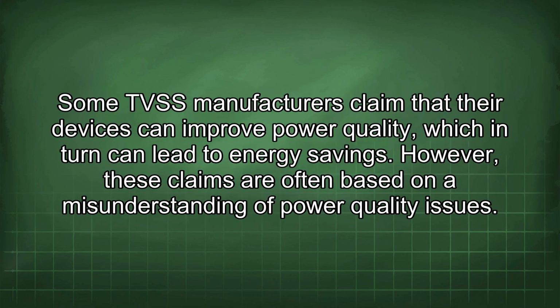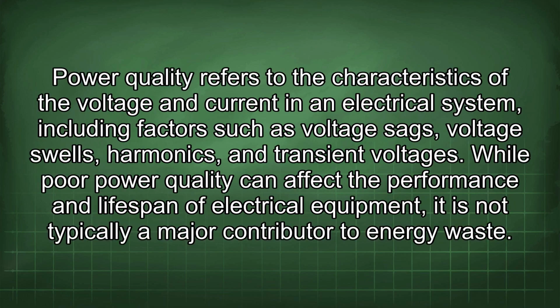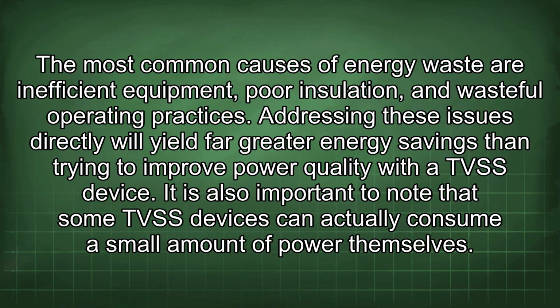Some TVSS manufacturers claim that their devices can improve power quality, which in turn can lead to energy savings. However, these claims are often based on a misunderstanding of power quality issues. Power quality refers to the characteristics of the voltage and current in an electrical system, including factors such as voltage sags, voltage swells, harmonics, and transient voltages. While poor power quality can affect the performance and lifespan of electrical equipment, it is not typically a major contributor to energy waste. The most common causes of energy waste are inefficient equipment, poor insulation, and wasteful operating practices. Addressing these issues directly will yield far greater energy savings than trying to improve power quality with a TVSS device.